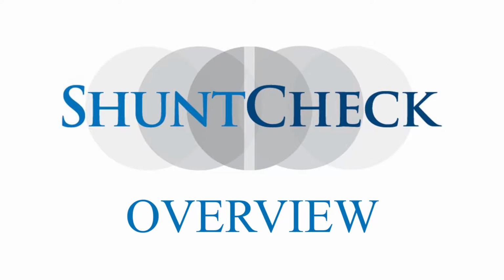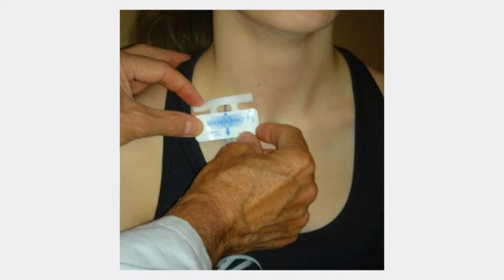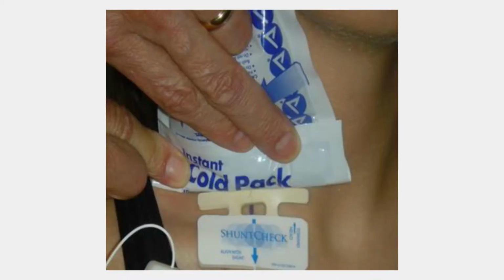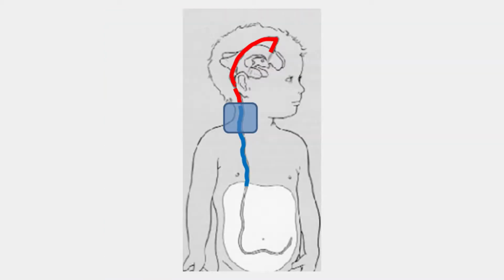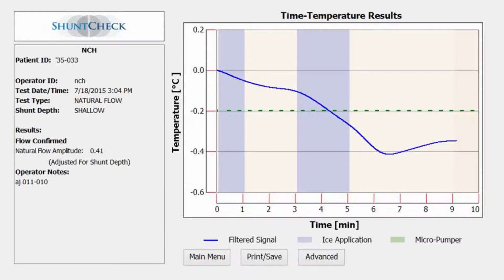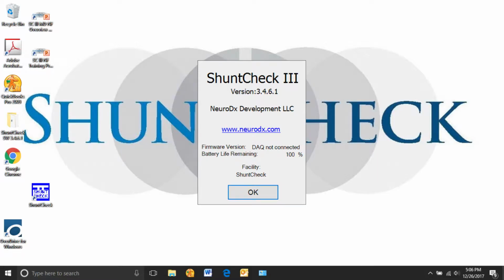ShuntCheck checks the flow in CSF shunts using a thermal method. The ShuntCheck sensor, a high-tech skin thermometer, is placed on the clavicle directly over the shunt catheter. The area just above the sensor is cooled with an instant cold pack, cooling the CSF right through the skin. If the shunt is flowing, the now cooled CSF moves downstream, reaching the ShuntCheck sensor, and registering as a characteristic temperature drop indicating flow. The ShuntCheck procedure is straightforward.